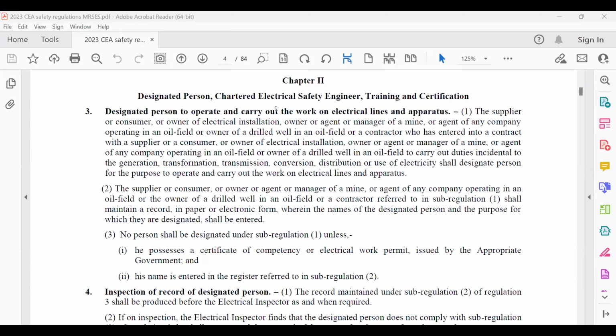My view is very clear in this regard, which I have been pursuing for many years. There has to be uniformity between the checklist and the inspection formats. It is very important, and each format should be classified for the particular type of installation. The same format cannot be used for all types of installations. For a public installation, say a cinema theater, you cannot use the same criteria as for a residential electrical installation. So there has to be categorization, and based on the formats given in IS 732 under clause 6, the format should be classified for different types of installations, and there should be uniformity between the formats given in the CEA regulations and those given in IS 732 or NEC.